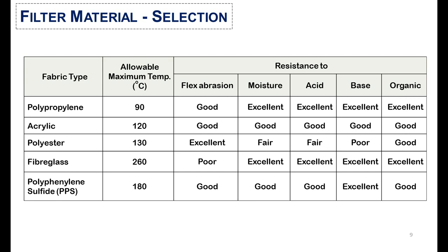If the service temperature is high, up to 260°C, then fiberglass is selected. However, fiberglass shows poor resistance to flex abrasion. Based on this criteria, you can select the right type of filter material for your bag filtration assembly.